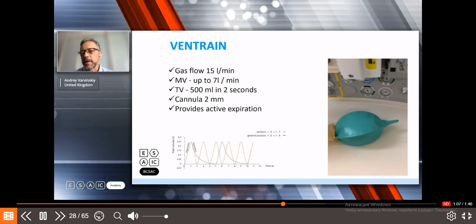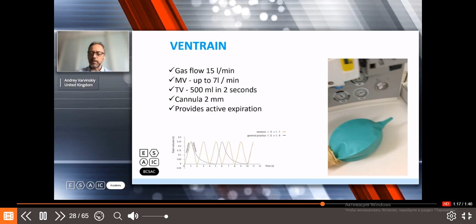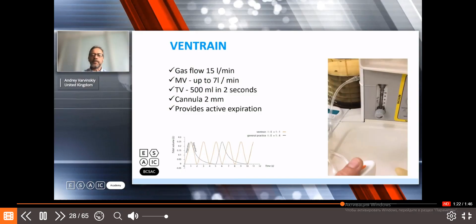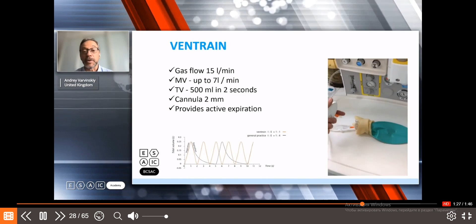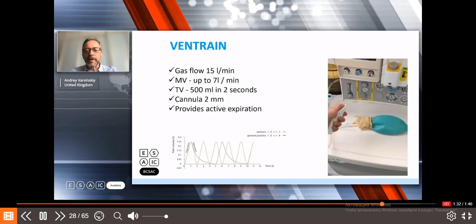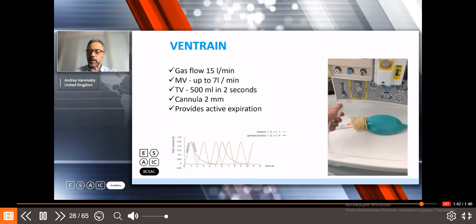There's no movement. By having a small narrowing inside of it, this device will, by the Bernoulli principle, provide a Venturi effect and will suck out the volume that was delivered with the previous inspiration. So it provides not only active inspiration but active expiration, as you can see, because this is a completely closed airway on this particular model. Okay, so that is Ventrain.